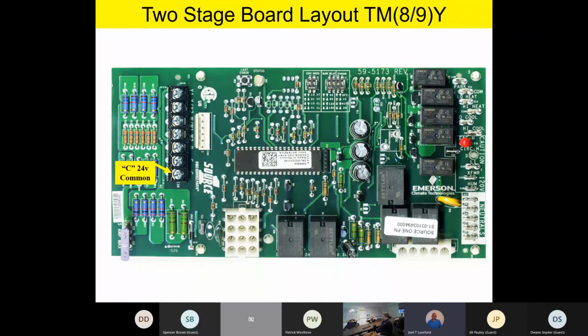Okay, as we move around the top of the board, we see that we have a last error button. This last error button allows you to retrieve flash codes and last errors. Now remember, team, this board will remember the last 5 errors, and you can cycle through them by depressing the button and cycling through your last 5 errors. If you want to reset the memory, you just hold that last error button down about 5 to 10 seconds, and it'll clear that service memory of those last errors.